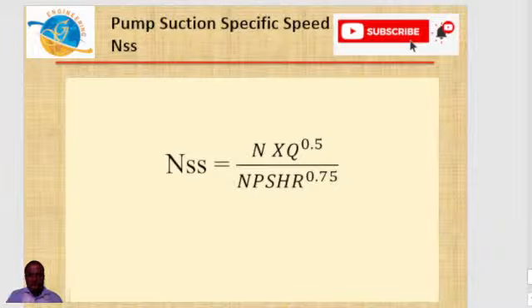So the pump suction specific speed is an indicator of the what? The impeller inlet geometry. It tells you how your pump can withstand some of these losses that occur at the suction or at the inlet of your pump.